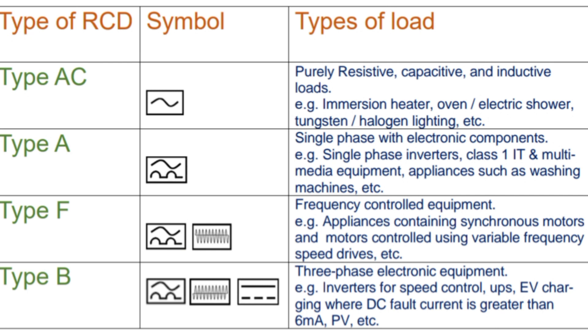The first type we are talking about is the type AC. Anytime you pick an RCD or an RCBO and you see this symbol on it, this simply tells you that this is a type AC RCD or RCBO. This type of RCD is used where the fault current is expected to be sinusoidal and at the same frequency as the supply. Examples of loads where a type AC RCD will be useful are immersion heaters, ovens, electric showers, and tungsten or halogen lighting. These systems must not come with electronic parts.